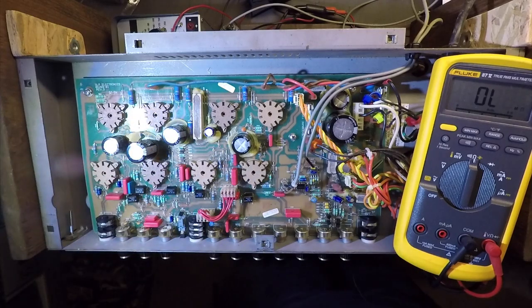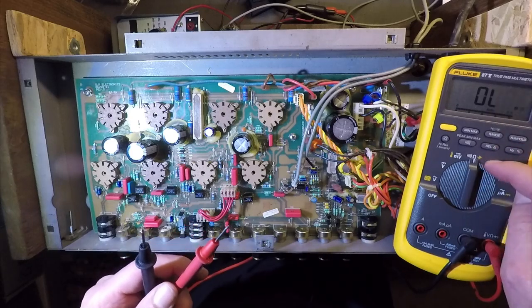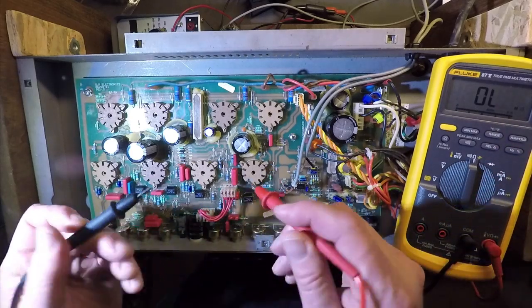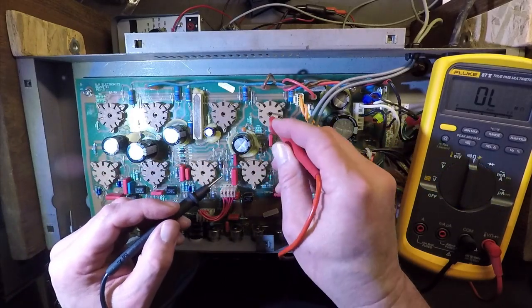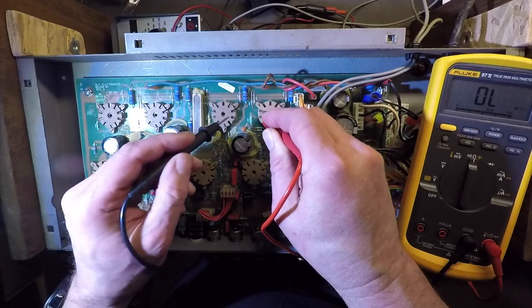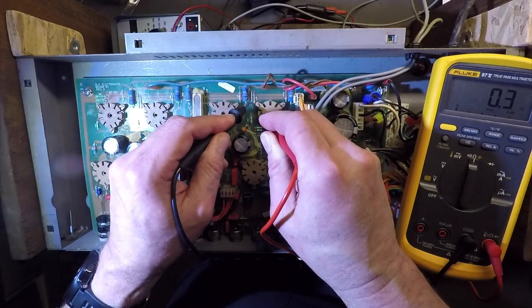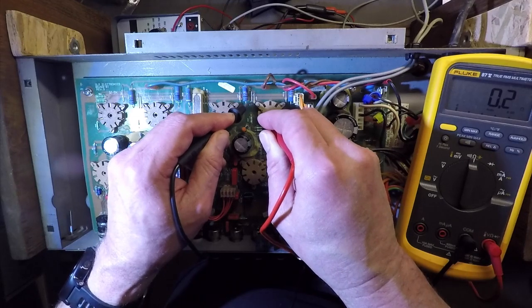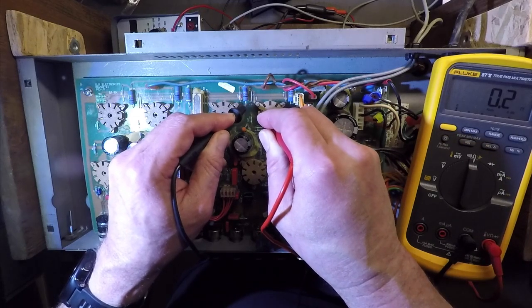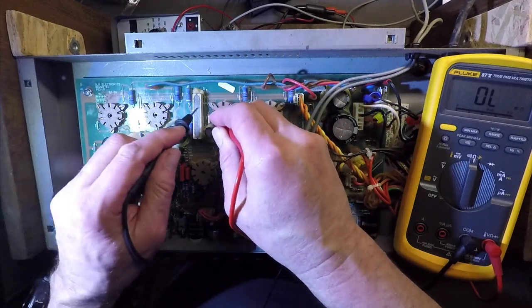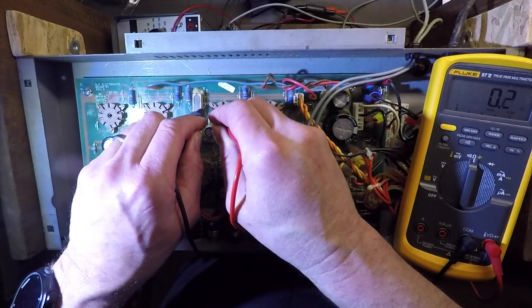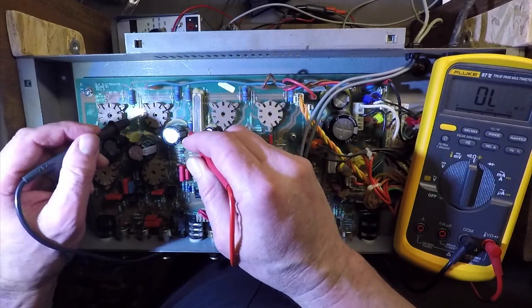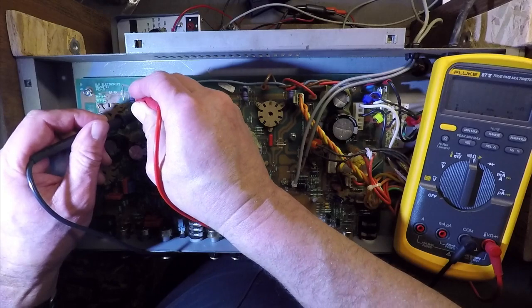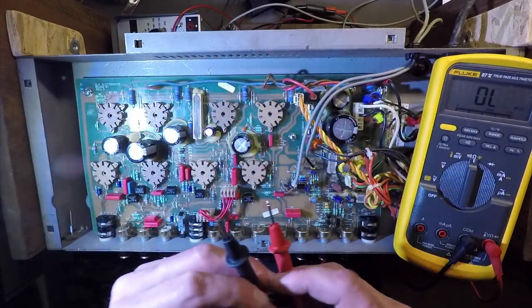But one thing you could do, and by the way, this amp is off, and it's been off for over a week, so it's easy to do this. I've got my multimeter set to resistance, and you can test to see if there's continuity when you have these jumpers. So I can just put my probe here on number 3 and on that jumper, and sure enough, if you look at the multimeter, it's a very low ohms reading, 0.2 ohms. Right, and the same thing we can do here. Let's try it there. Low ohms reading. Let's try it over here. Same thing. Right, so why do I do that?